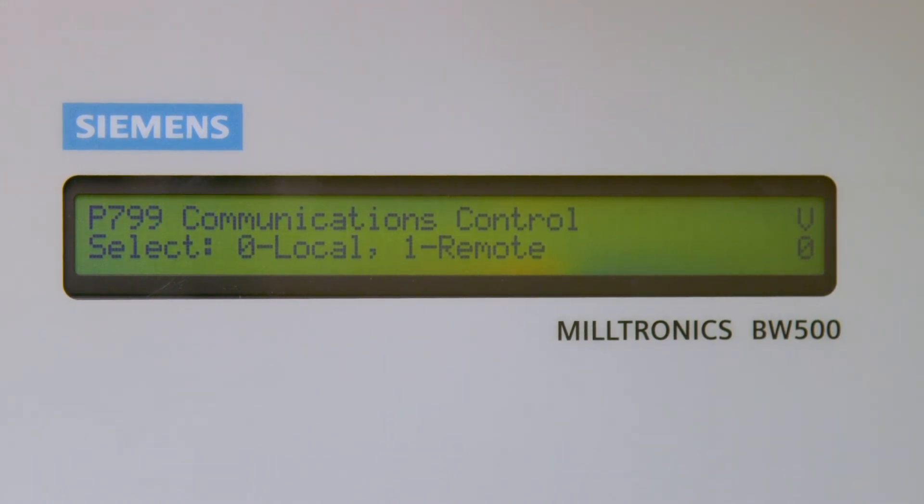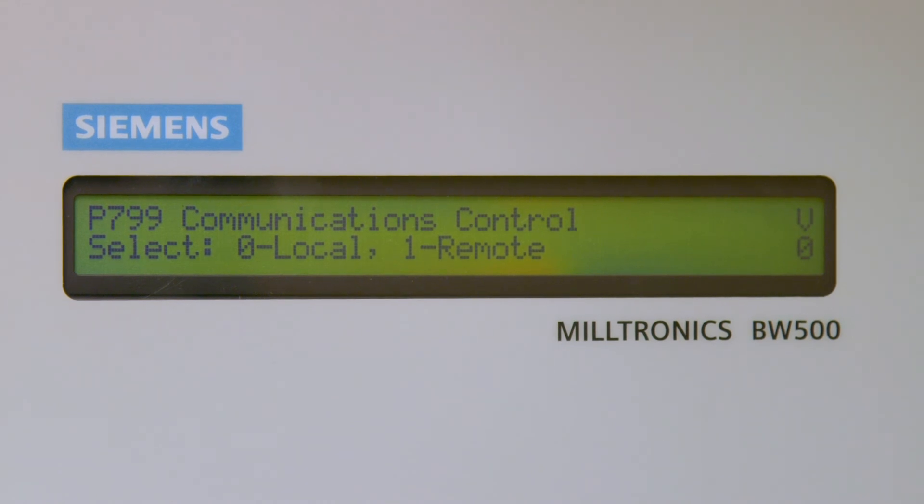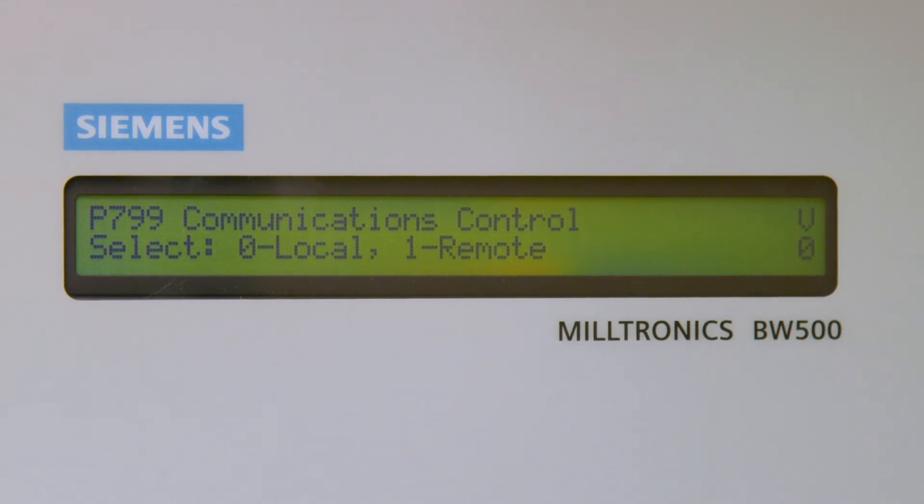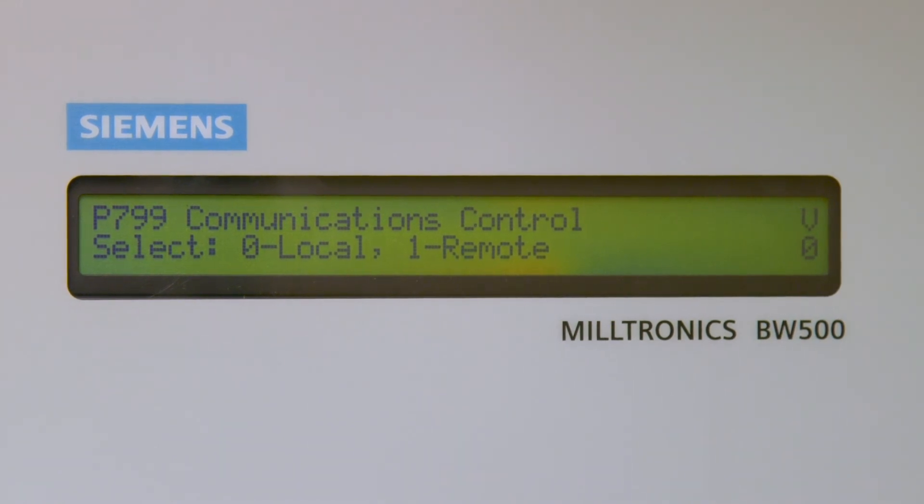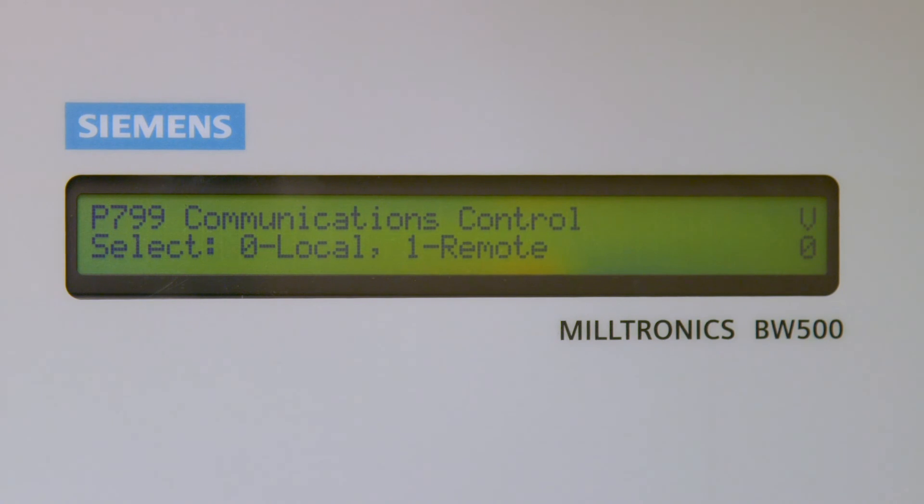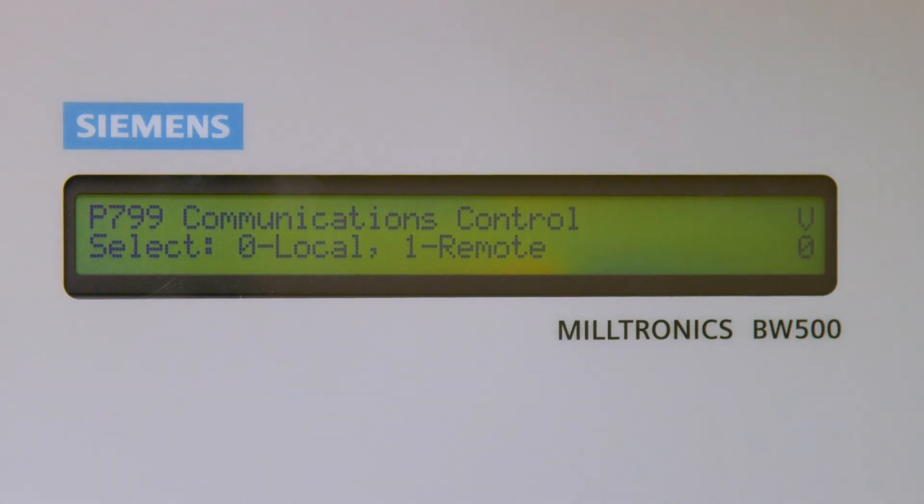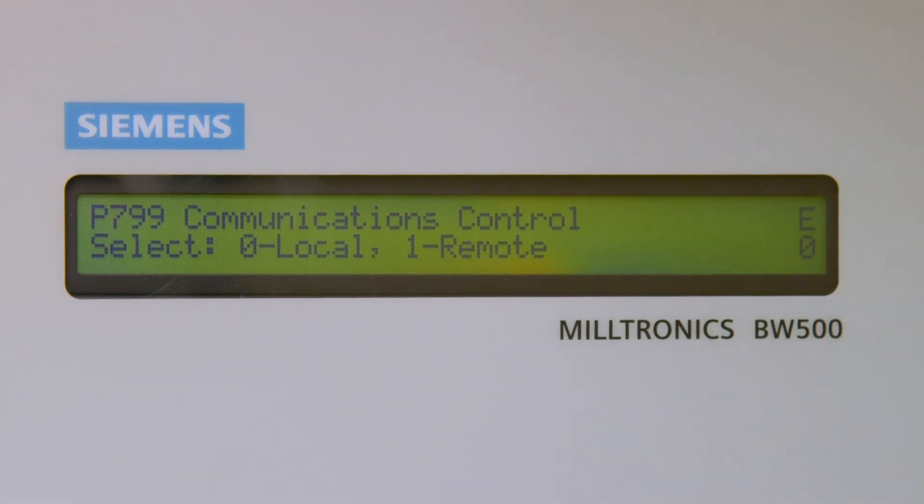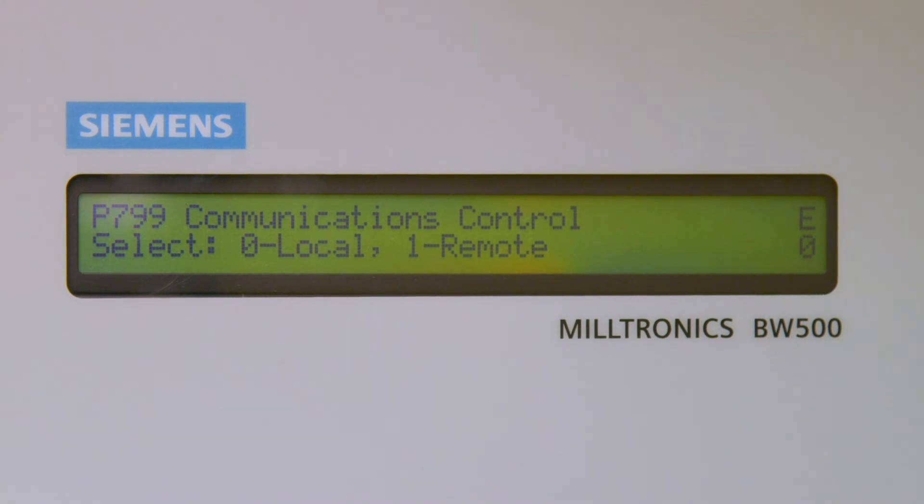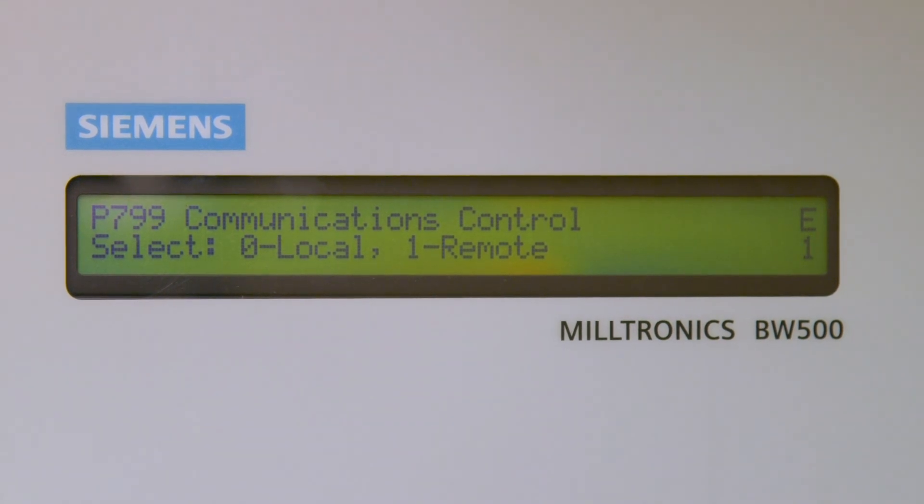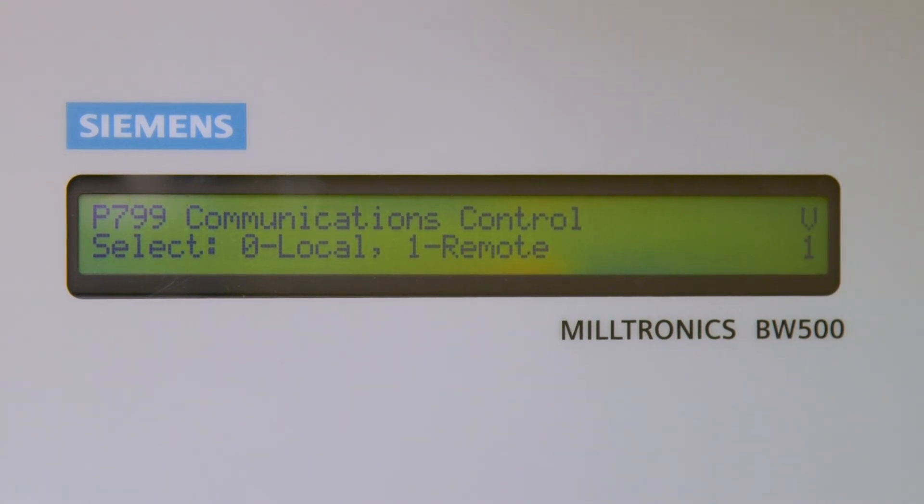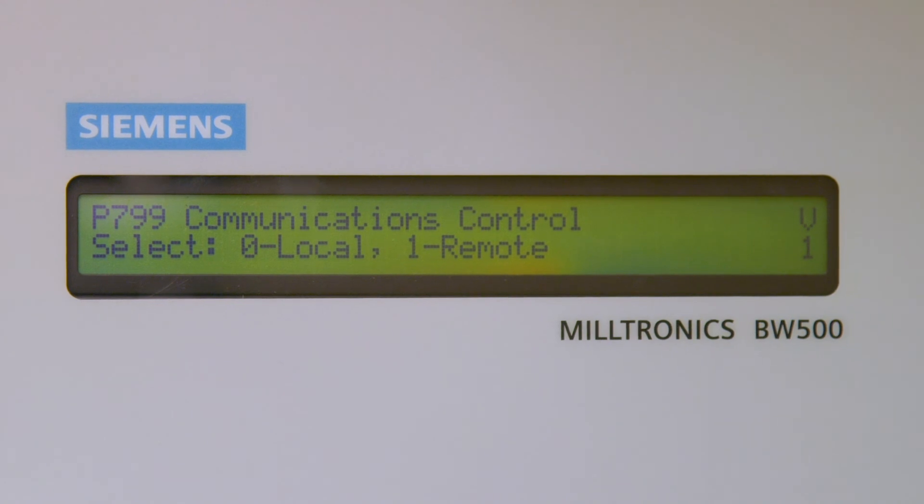If the value of P799 does not equal 1 for remote, then push the Enter key on the BW500 keypad to change the character on the display in the top right-hand corner from a V to an E. Enter 1, then push the Enter key. Push the Run key to put the BW500 back in the Run mode.